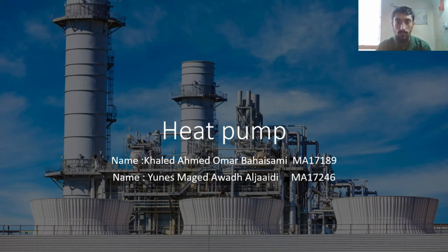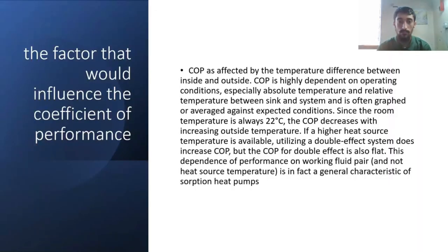I will continue from here for the heat pump experiment and for the discussion. We discussed the factors that would influence the COP, and we found that the COP is affected by the temperature difference between inside and outside. The COP is highly dependent on operating conditions, especially absolute temperature and relative temperature between the sink and the system, and it is often graphed or averaged against expected conditions, since the room temperature is almost 22 Celsius. The COP decreases with the increase of outside temperature.